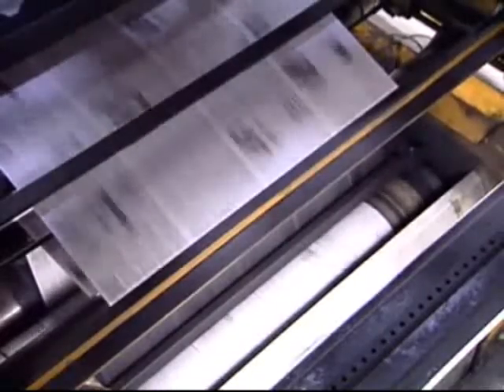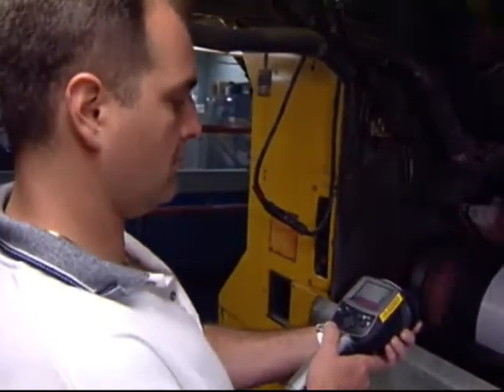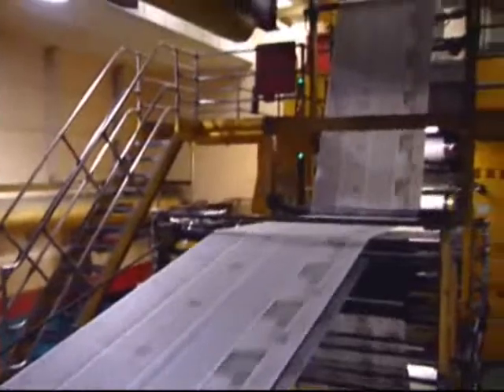Nobody wants yesterday's newspaper. I need that press running every night. Printing presses have hundreds of mechanical and electrical components. As they approach a failure state, increased heat signatures can be seen using FLIR infrared cameras. FLIR cameras allow technicians to see potential press problems before downtime occurs. So maintenance costs are reduced, and the presses keep on running.